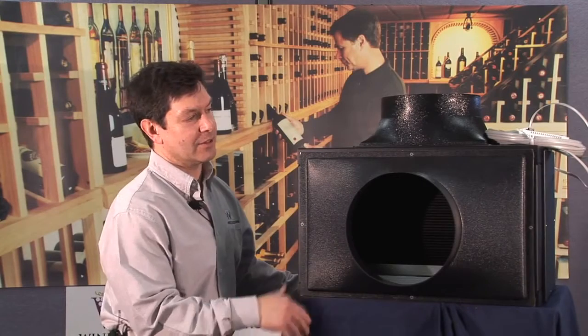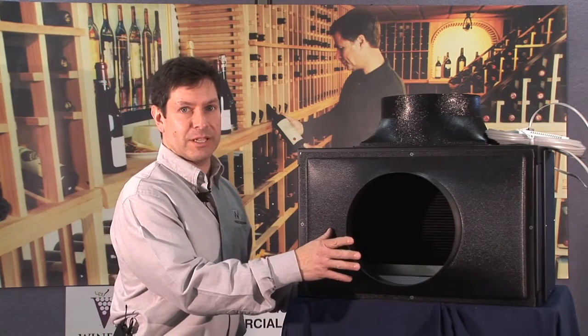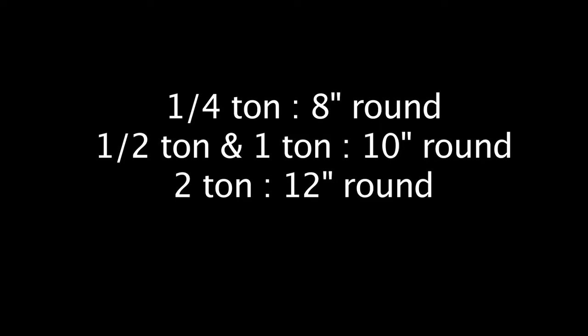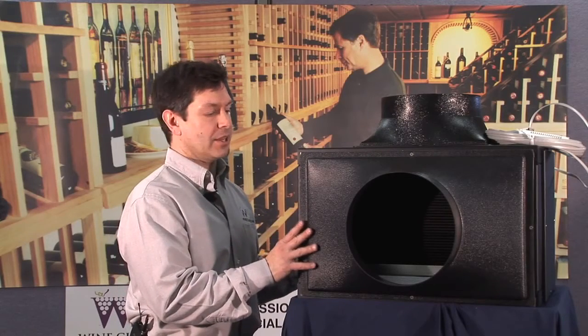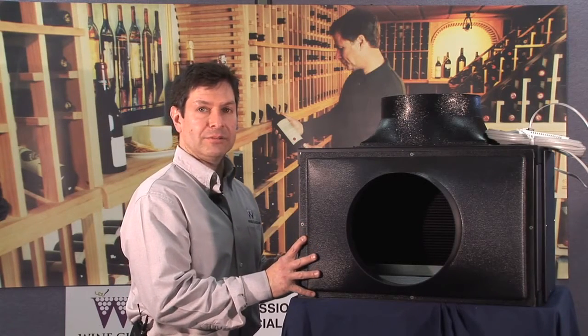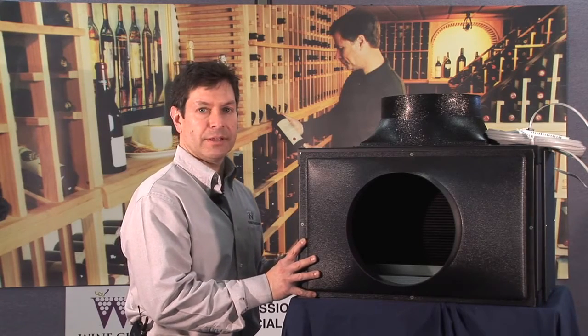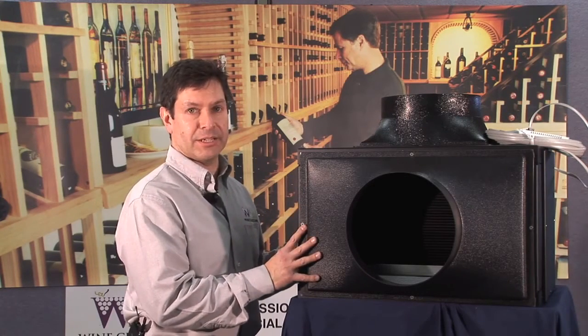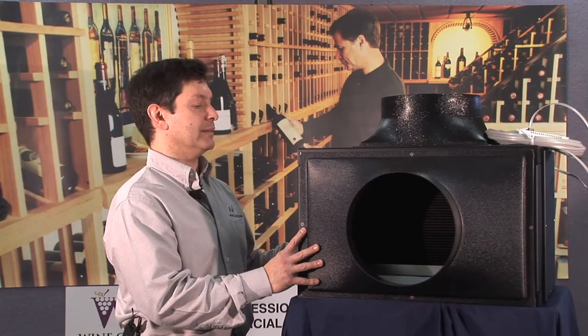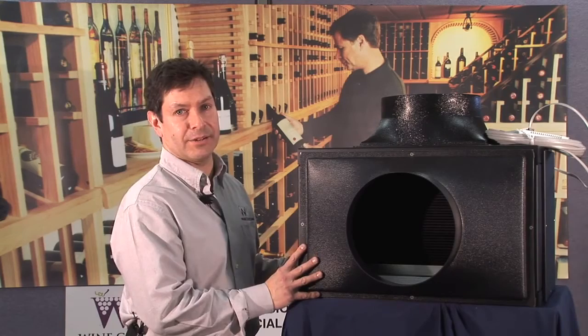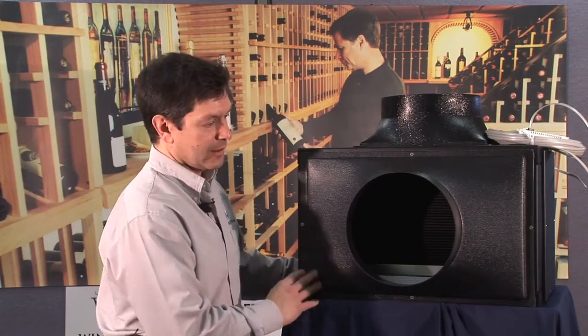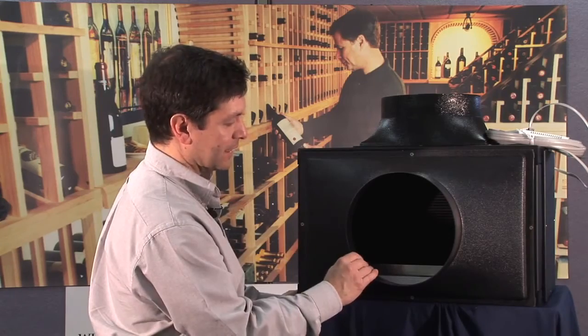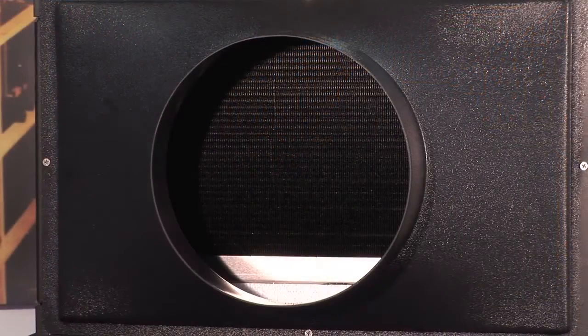Turning the system around, you can see the return duct collar as provided with the units. For the quarter ton, it requires an 8-inch round. For the half ton and 1 ton, again, our standard 10-inch round. And the 2 ton goes up to a 12-inch round duct collar supplied with the unit. The systems as a whole are ETL labeled to UL standard. So the system, both the fan coil and the condensing unit, have those labels to an ETL and CSA standard. You can see the coated coil as part of the design and the all-aluminum construction.